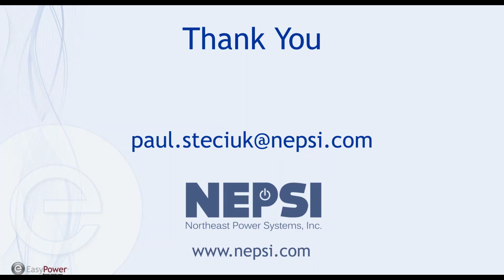All right. The first is from Rolando. He's got a question as a follow-up to the first slide that we discussed. He says, why would the current limit violation not be a concern when IEEE actually provides this limit? Why then is there a current TDD limit when it won't be a concern? Well, first of all, the total distortion limits defined by 519 are defined at the point of common coupling.